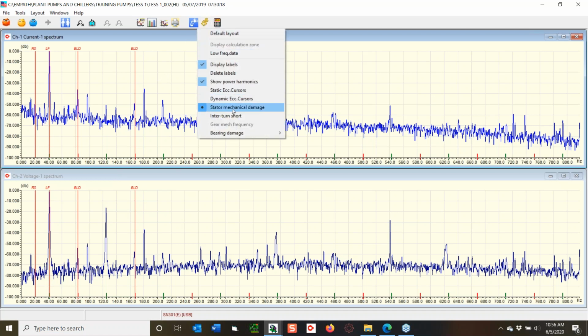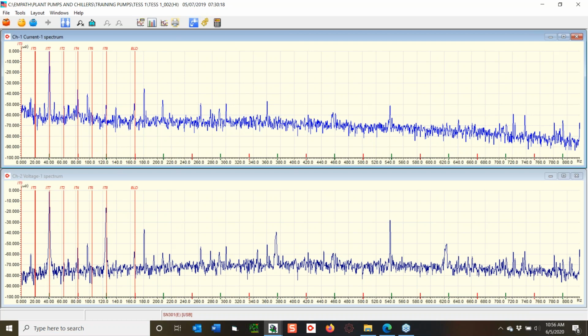But I can come in here and let's take a look at interturn short. Now, what we discovered, and the paper is being presented this week through IEEE, is that I can see interturn shorts here even though the motor hasn't failed. Now, if it's on a drive and I have an actual short, it trips off. But what happens is I can have discharges going on between conductors and things like that, and that will interrupt the magnetic circuit, and it looks like arcing or a short. So what I want to do is verify that I have peaks outside, like this peak here and a couple other peaks. And if they don't associate with anything else, then that just means that the drive isn't tuned properly, or, and I know that was the case, they selected the wrong filter. That's kind of what I'm looking at there.